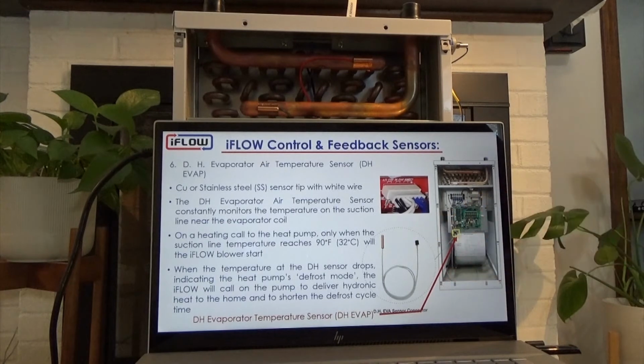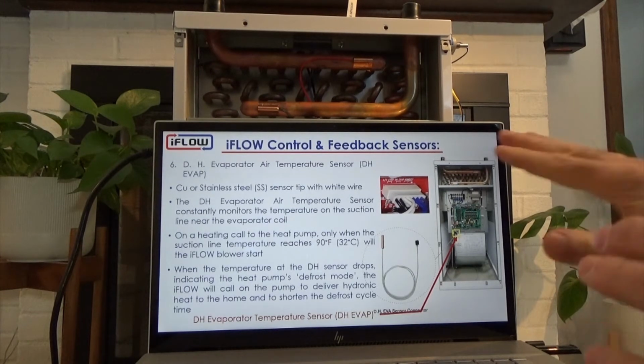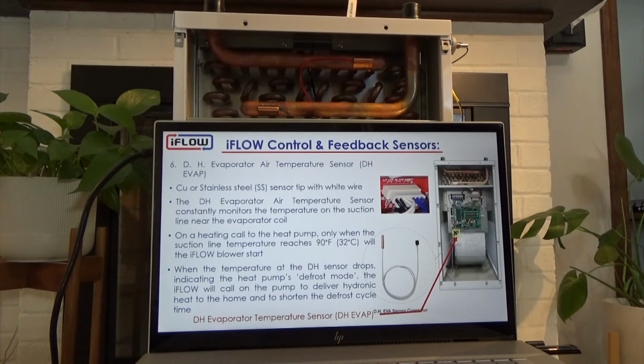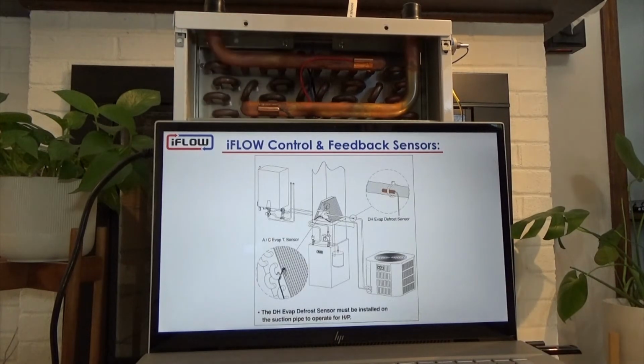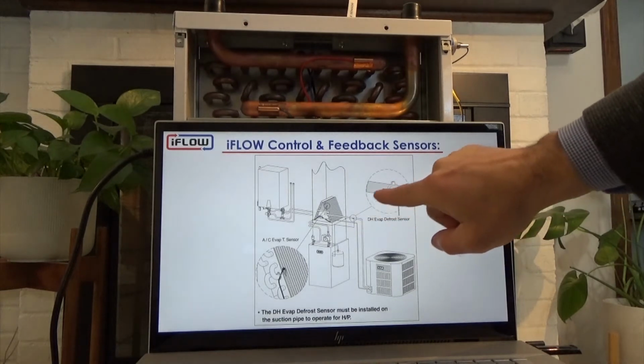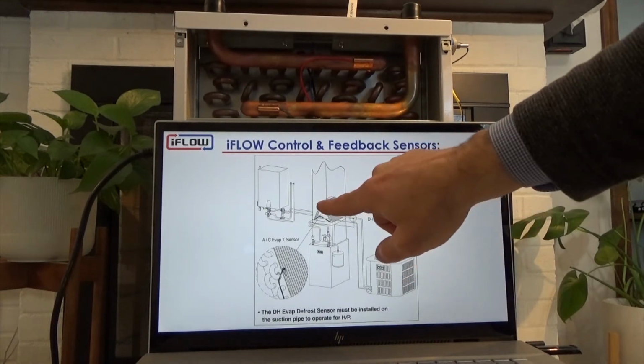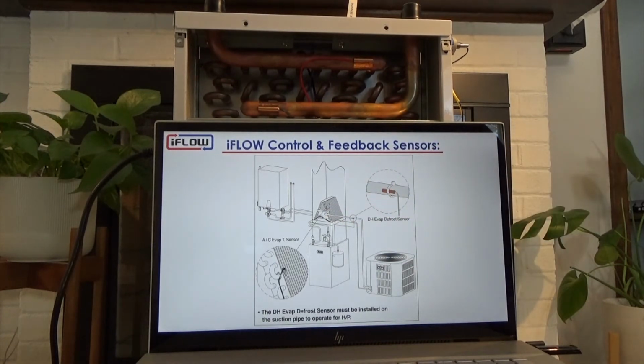So the DH evaporator sensor is critically important when we're using a heat pump. The system will not work without it. We don't include it in the box because at this point most of the systems will be installed with regular air conditioning and not necessarily heat pumps. So it is an optional item, but if you are wiring the iFLOW or combining the iFLOW with a heat pump and a gas backup system, either a tankless or a tank or a boiler perhaps, then you will need to order the DH evaporator sensor to make your system work. As I mentioned, it connects to the suction line on the line set feeding your evaporator, and then connects back to the unit.